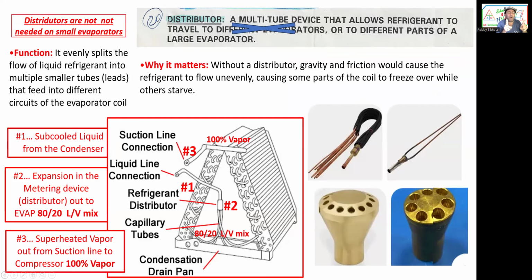A small evaporator doesn't need it because we don't have pressure drop between the beginning and the end of the evaporator. I know in the first video I said the pressure is the same on the low side. It's not. We say it is, but on a large evaporator, pressure changes a little bit.